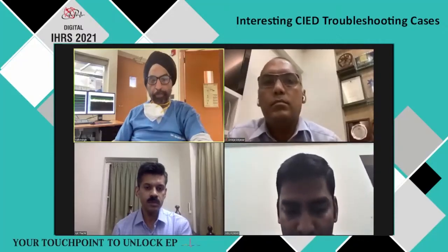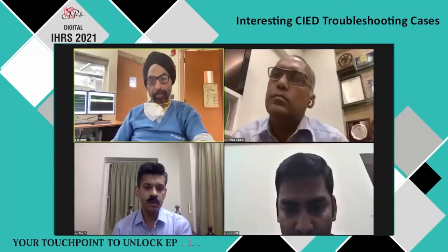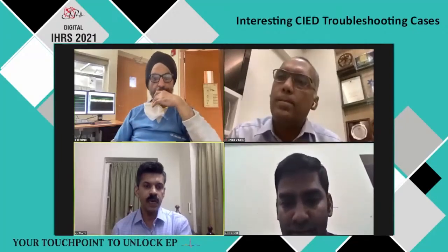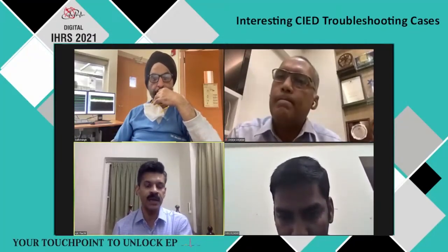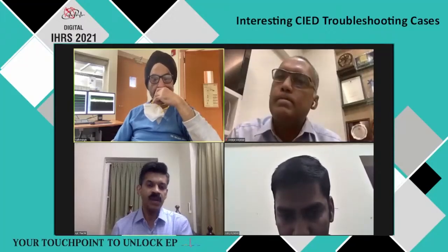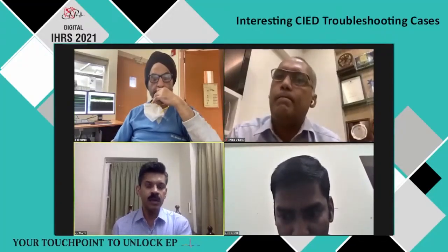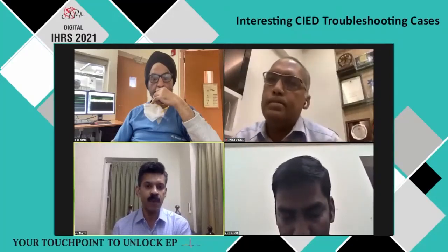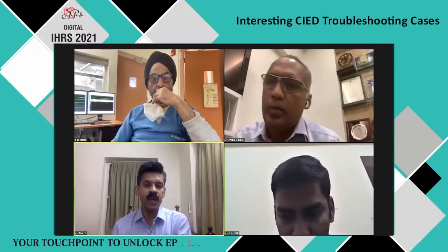Right. Because I've seen a few PMTs and the BIV pacing was still happening. I'm talking of one patient who had a PMT. Yes, it would happen so long as it doesn't violate the LV upper rate interval. It has a separate LV upper rate interval and a separate RV upper rate interval. The difference between the two is the AV Wenckebach feature is applied to the RV upper rate interval, but it is not applied to the LV upper rate interval. And the LV either tracks at sensed AV delay or it doesn't track. Right. And on the programmer, you could find that it was RV pace, not BIV pace.